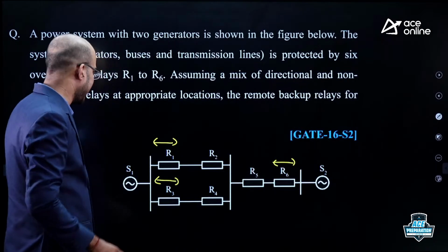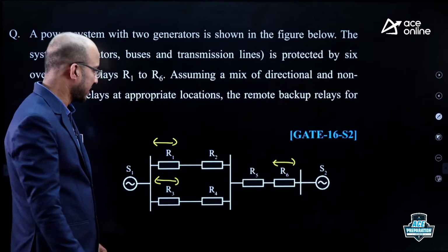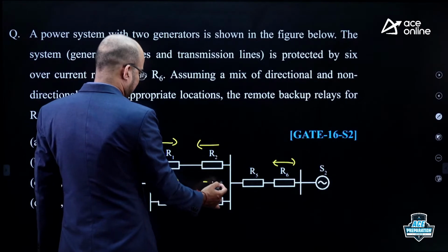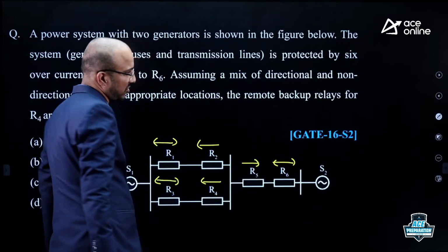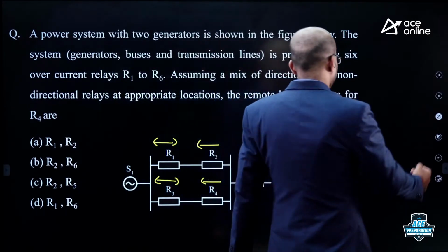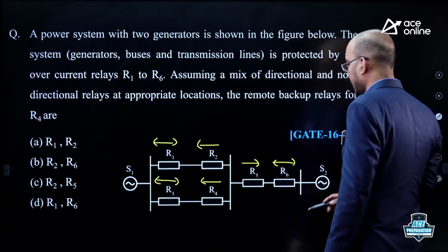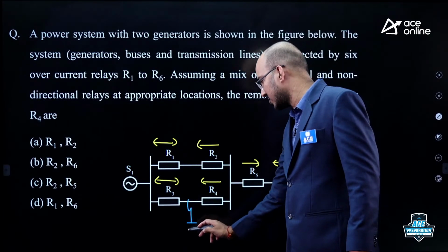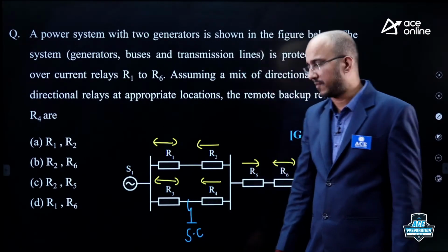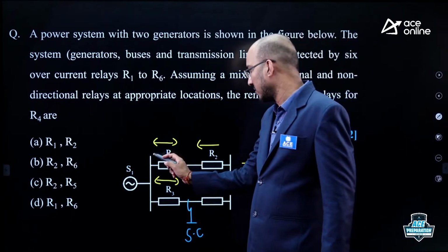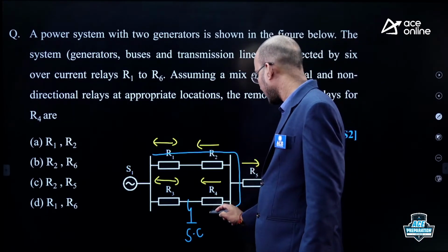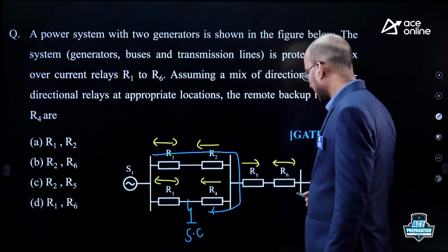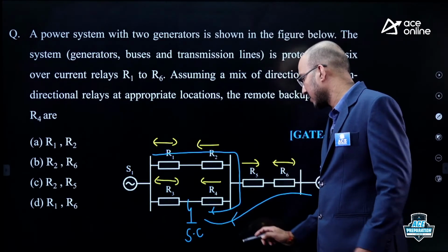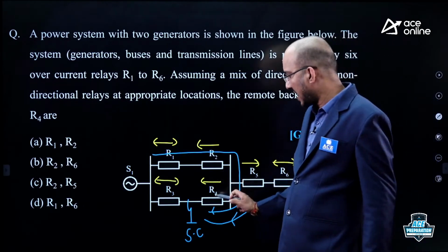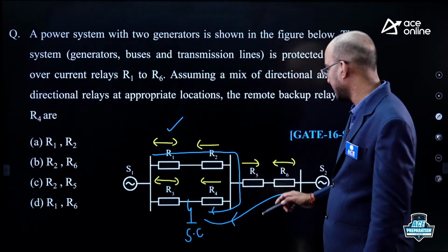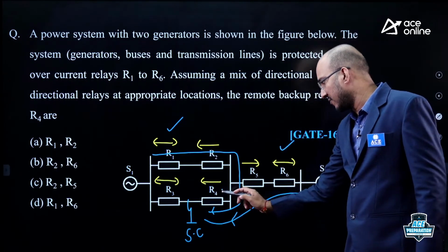So, we have identified that R1, R3, R6 are non-directional, R2 is directional, R4 is directional and R5 is also directional. Now, when R4 has to be operated, suppose there is a short circuit fault here, then R4 has to operate. Now, observe the path for fault current here. This is one path and this source will deliver in this path. So, which relays are sensing? R4 is sensing, R1 will sense, R6 will sense and R4 will sense.